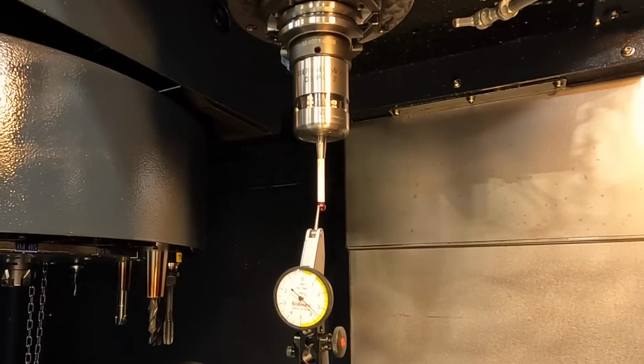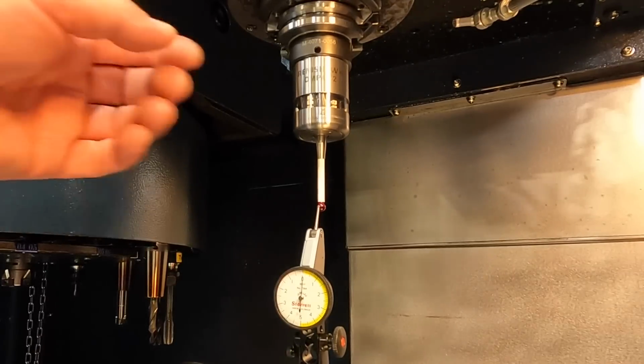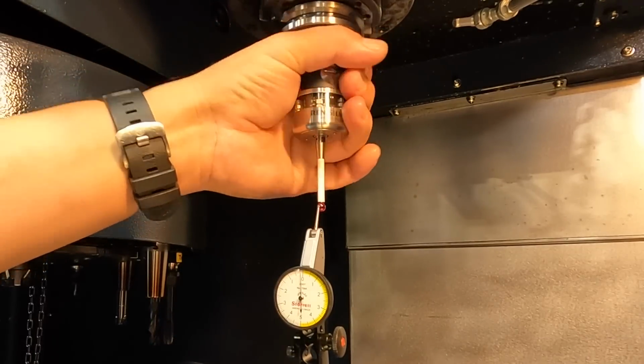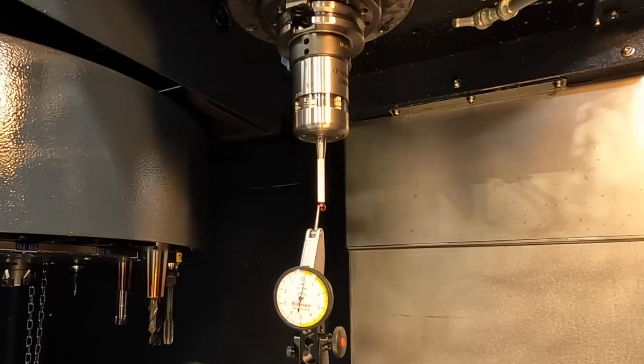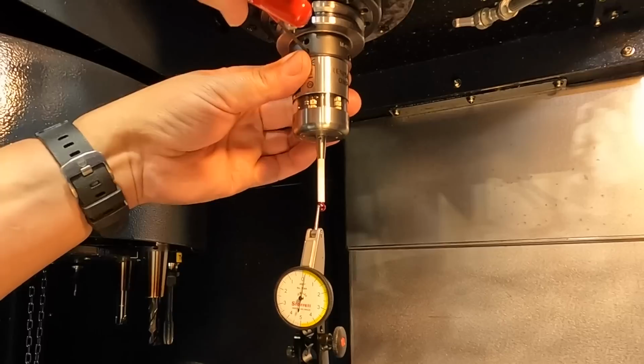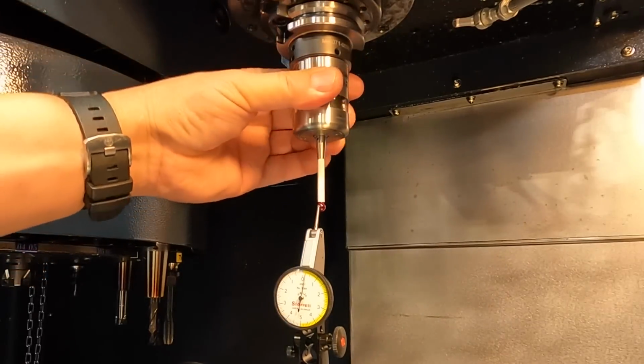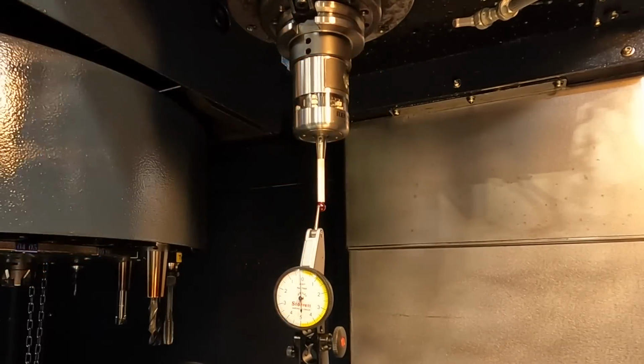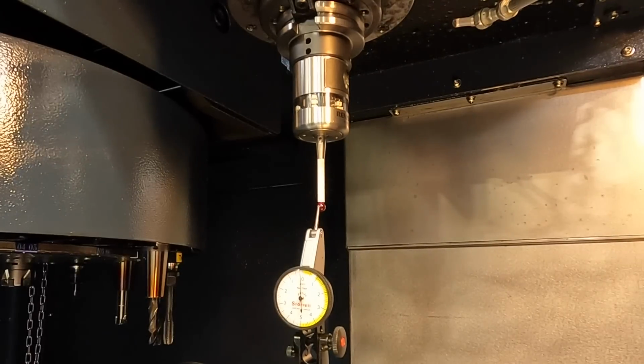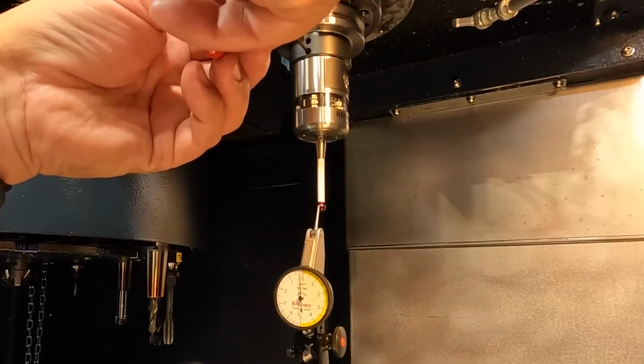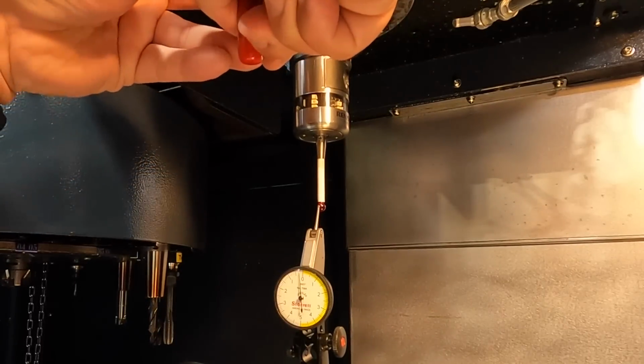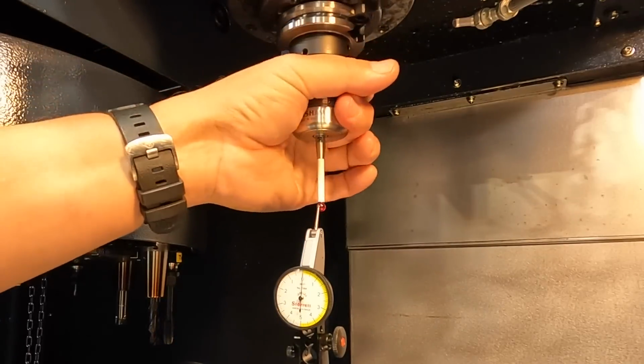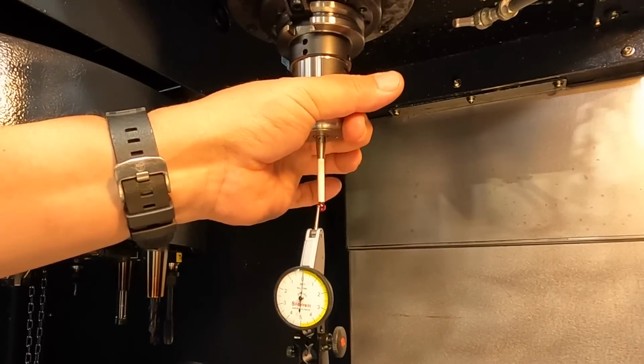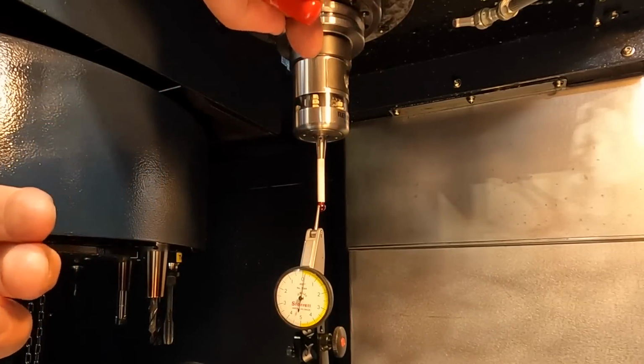I'm going to go ahead and adjust that indicator again and try to get a little closer to 0. I'm just using the table movement here to try to get it lined up. Looks like 4/10. So we'll start with our high and see if we can get it pushed over any more. Nope, I'm gonna have to crack it loose. And the instructions that they gave me is 0.5 thousandths or less. I think on the Renishaw website it said 1/10. So when I cracked that one loose, it went a little too far. So I'm going to go back in with it.